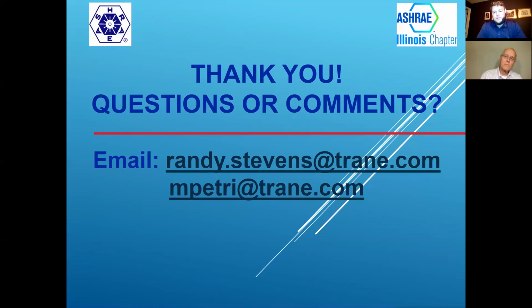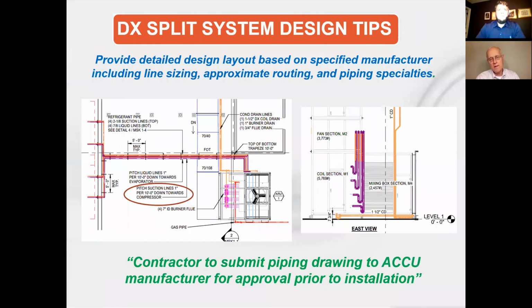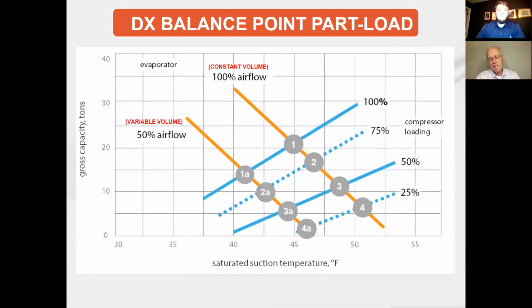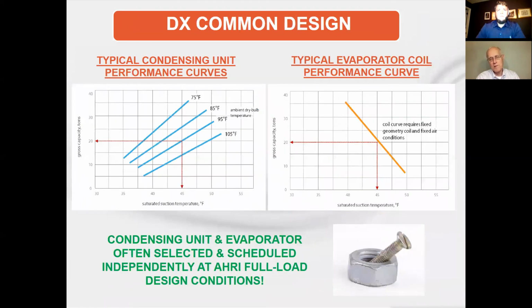So in strict terms of refrigeration piping, if you look at the question, there would be really no difference in your actual refrigeration piping in a standard application versus a low ambient application, right? Could you touch on flooding the condenser for low ambient conditions, for ultra low ambient? Okay, so that's a technique where the surface of the condenser coil is reduced by flooding the condenser coil with refrigerant, if that makes sense. You figure that most condensers have 3/8 inch tubes in them, so they hold a certain volume of refrigerant. The surface area of that refrigerant, if you fill the tube halfway full of liquid, you've reduced the actual heat transfer area that's left.